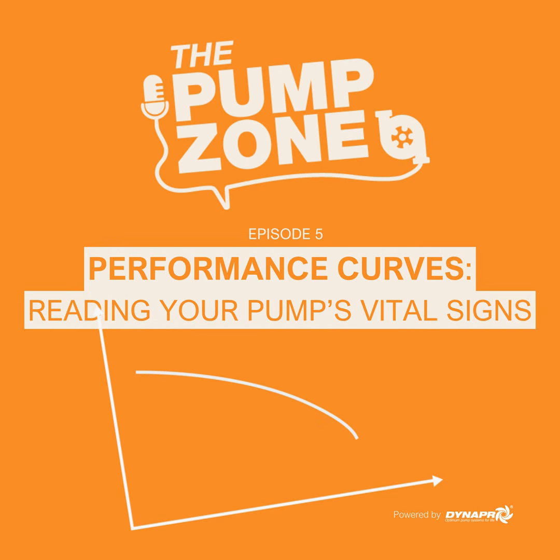Which is exactly why operators can't just run these pumps wildly. But real-world system demands fluctuate. Right. And you don't want to buy a new pump every time conditions change. So the sources say operators rely on families of curves by adjusting impeller diameters or motor speeds to alter performance. You shift the curve to safely hit different points. We divide these operating zones up. The BEP is your ideal spot. Then you have the POR, the preferred operating region, which is a bit wider and safe for continuous use. And then there's the AOR, the allowable operating region.